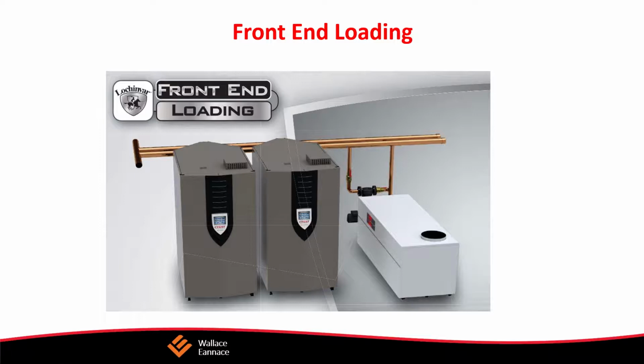A 70-degree design difference would give you, for example, in a house, a 100,000 BTU heat loss. That's basically the heat that's leaving through the roof, through the walls, infiltration, and also through the floors. A 35-degree design difference will give you a 50,000 BTU heat loss. Same situation for the same building. Now let's face it, it's 35 degrees outdoors a lot more often than it's 0 degrees outdoors. So how do we size the boiler? Do we use a 50,000 BTU boiler, or do we use a 100,000 BTU boiler?